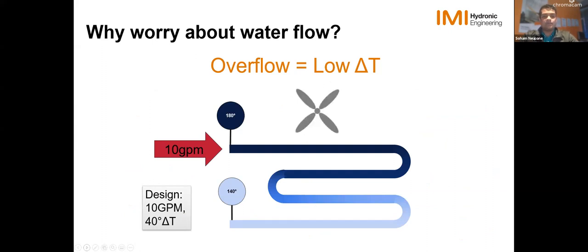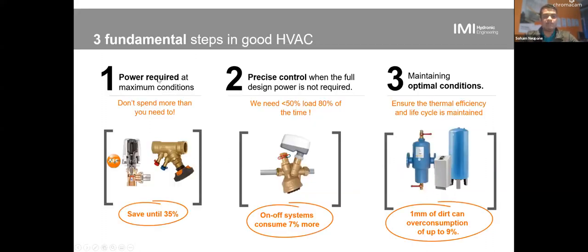And before I get into this, today we're going to focus mostly on the power required at maximum condition. That's the design flow. And when we don't have proper balancing, what happens? We overflow, right? So why worry about the overflow? Because, we hear this a lot in our ASHRAE conversations and journals, this is a topic of interest where you start seeing low delta T issues for your chillers mostly.